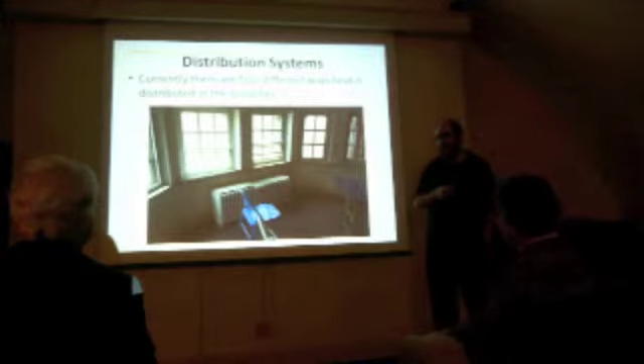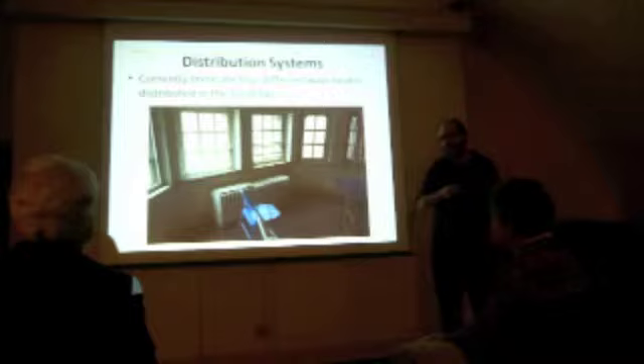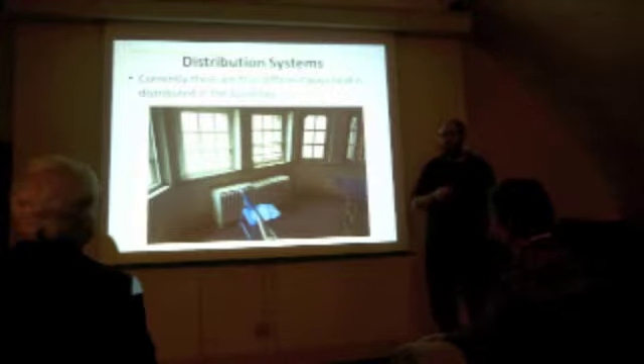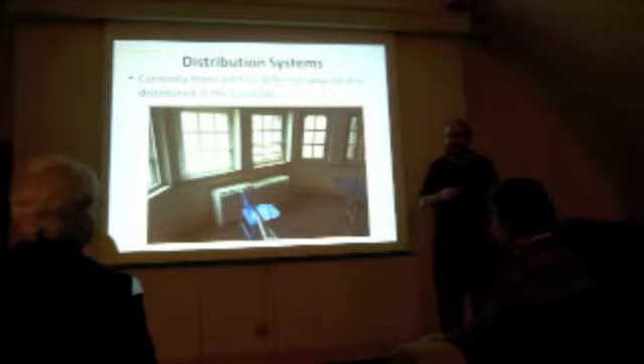And then your blower system, even in the one before that, it's heating the ceiling in a way, and then there's more energy needed to pull it down below and circulate. In a shorter room, that is a question of whether you're just heating the ceiling directly. In the sanctuary where those are, the ceiling is far enough up that you're heating the wall, and that's certainly true, but you're not going to get the ceiling very much.